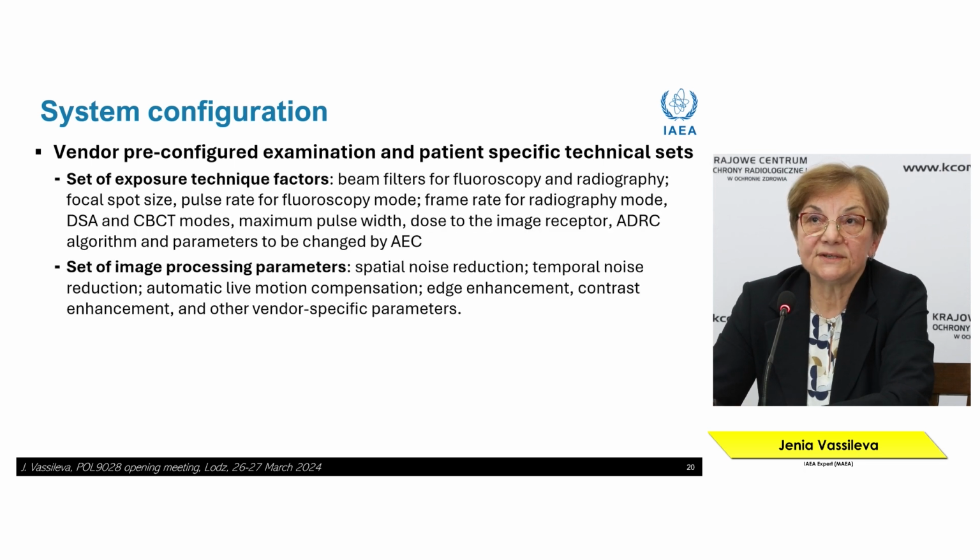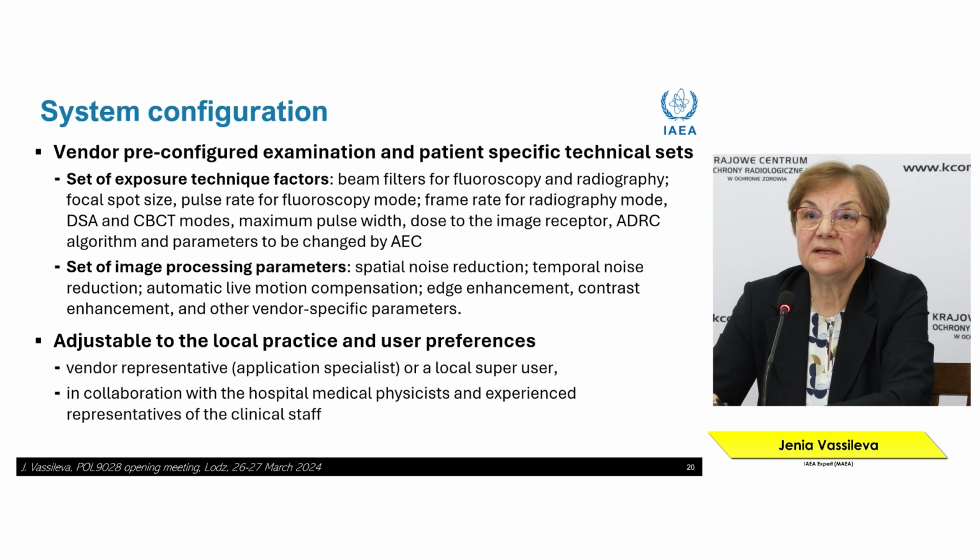System configuration is something that the staff cannot control. This depends on how this is manufactured and how this is set by the vendor, but it's very important for this to be checked at the commissioning and the acceptance of the new imaging equipment, to know the equipment and the features.